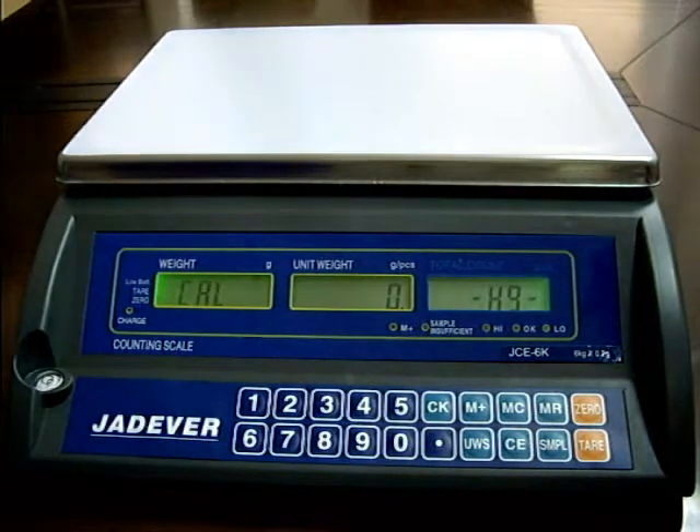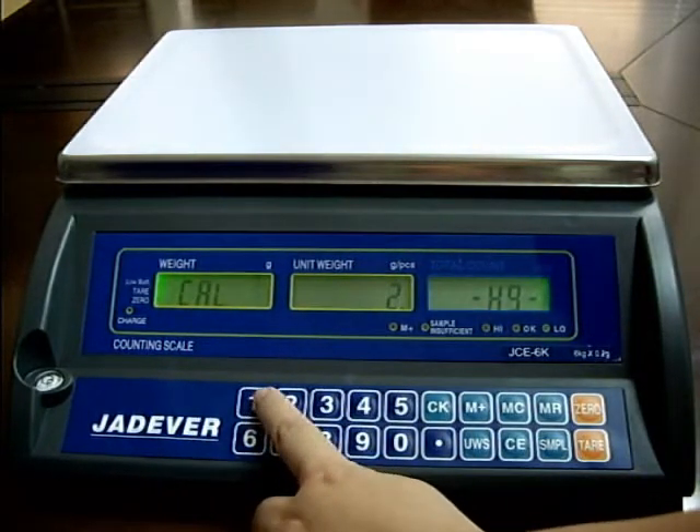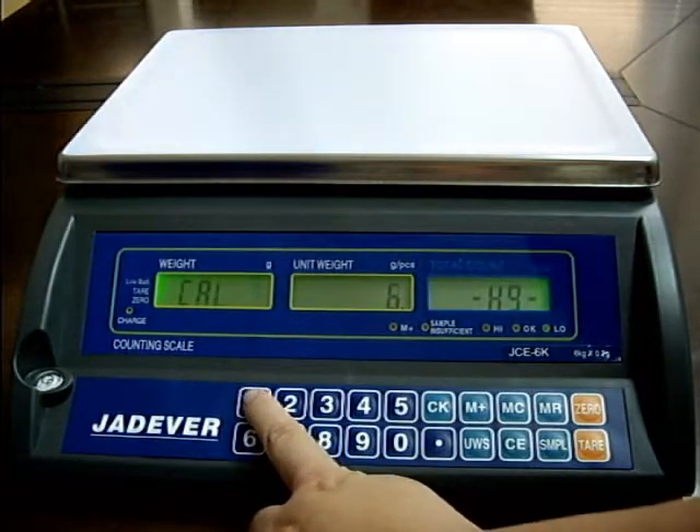Wait until CAL flashes, then press 1 to select the calibration weight. Options are: 1 third of full load, 2 thirds of full load, or full load.